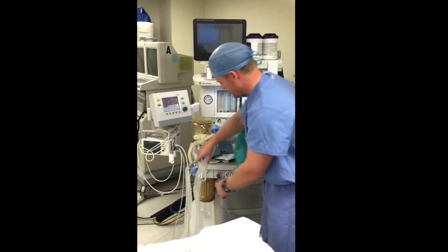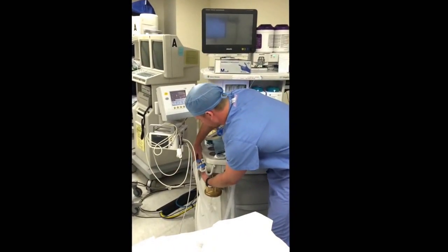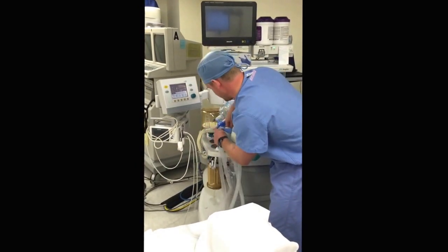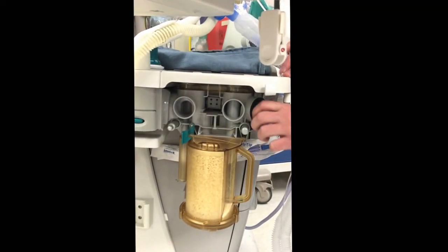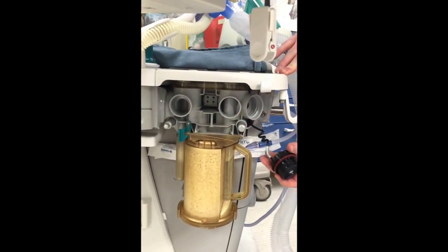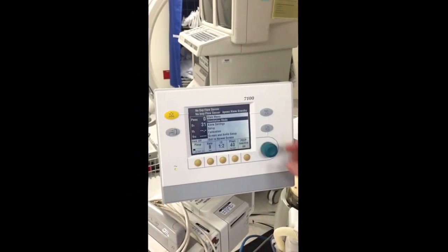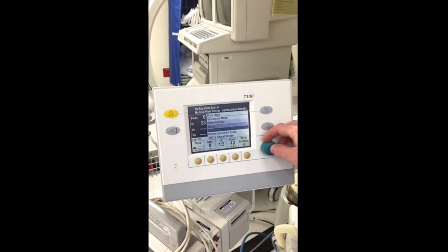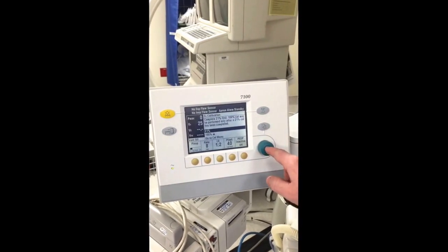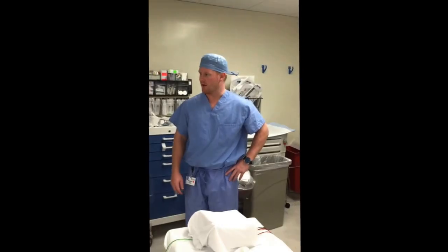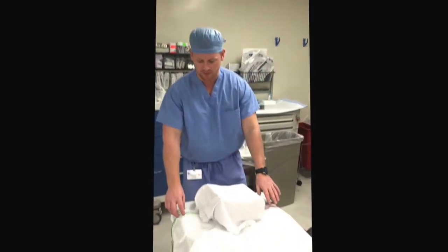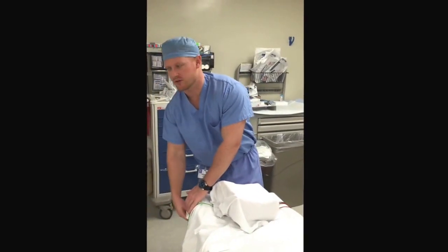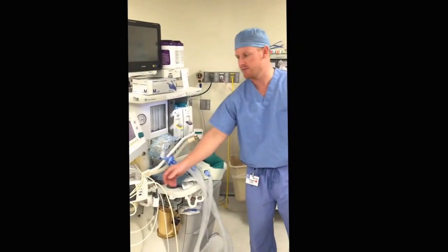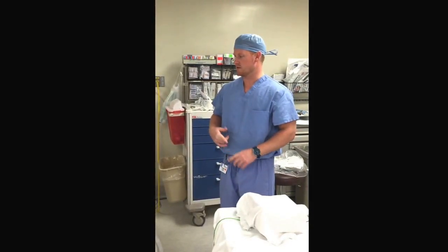The next thing you check, and these will be different on each machine, is the O2 calibration system. On this machine, it's covered down here, and then on the vent, leave the calibrator open to room air, go to O2 calibration and hit 21%. While that's calibrating, there's other things you can do in your room, like setting up your EKG leads, your blood pressure cuff, your pulse oximeter, and make sure that you have your airway, your laryngoscope, oral airways, and everything set up for your intubation. So it takes a few minutes to calibrate.